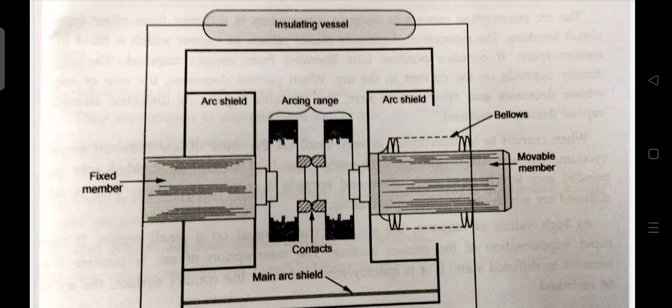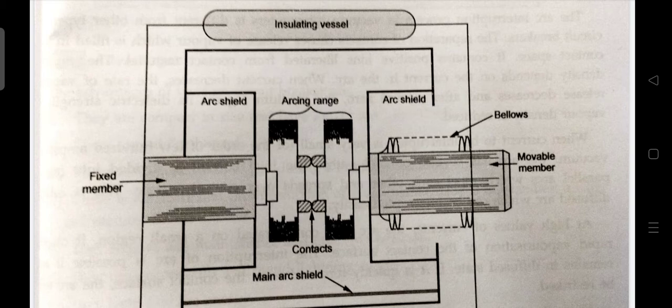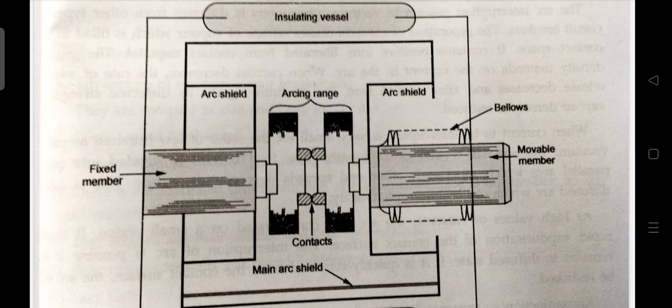The movable member is connected to the control mechanism by stainless steel bellows. The glass vessel or ceramic vessel is used as the outer insulating body. The arc shield prevents the deterioration of the internal dielectric strength by preventing metallic vapor falling on the inside surface of the outer insulating cover.